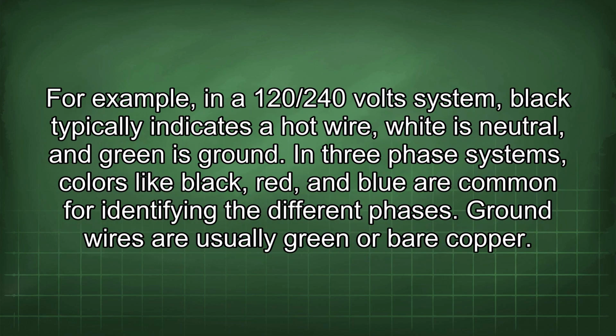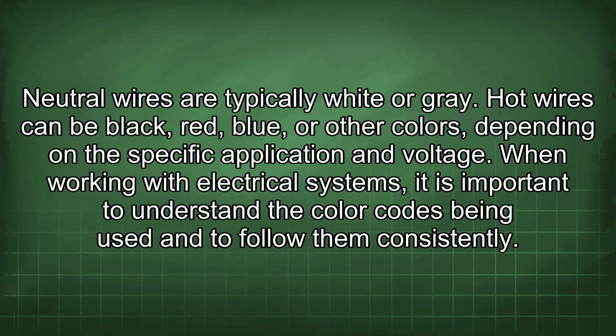For example, in a 120/240 volt system, black typically indicates a hot wire, white is neutral, and green is ground. In three-phase systems, colors like black, red, and blue are common for identifying the different phases. Ground wires are usually green or bare copper. Neutral wires are typically white or gray. Hot wires can be black, red, blue, or other colors depending on the specific application and voltage.